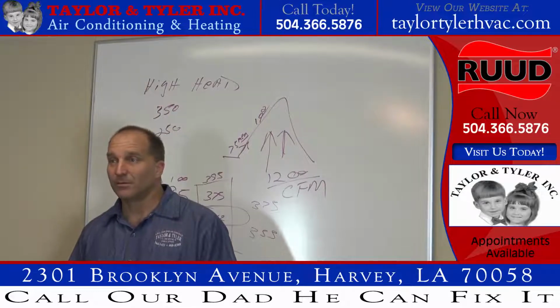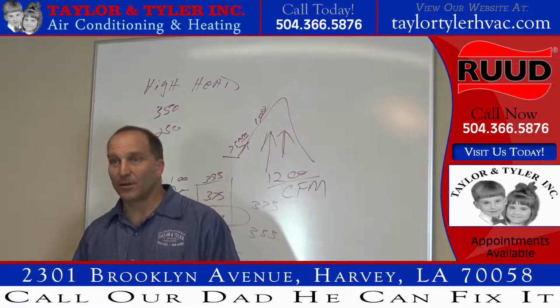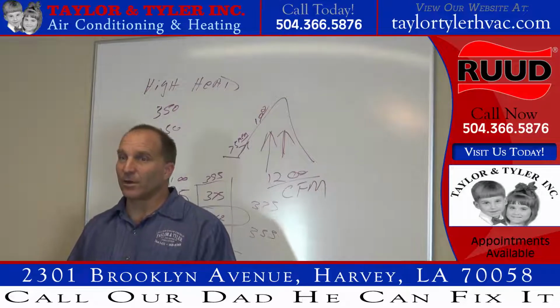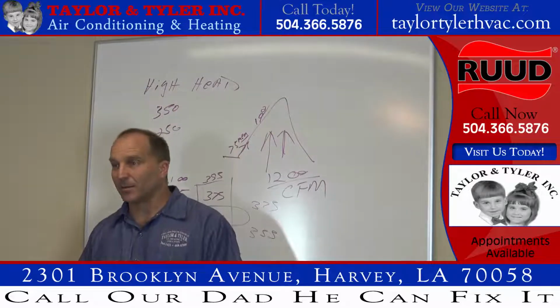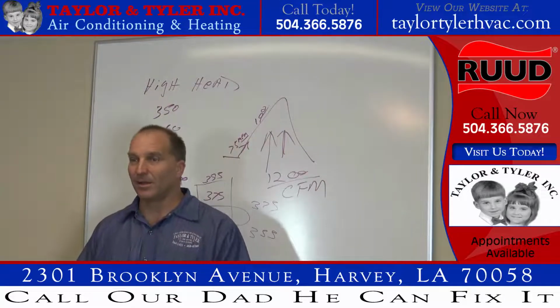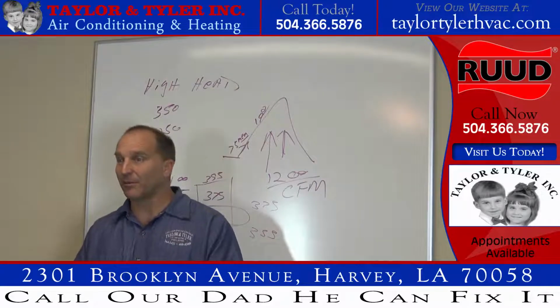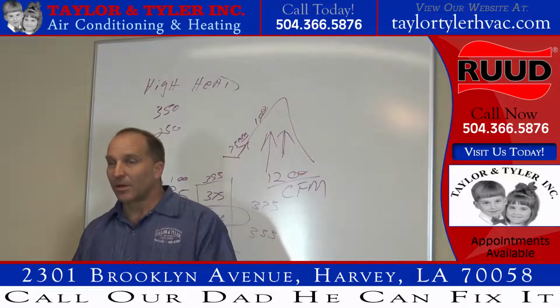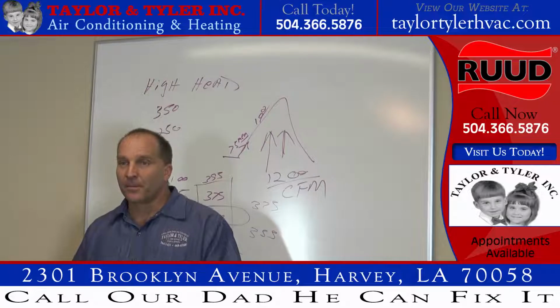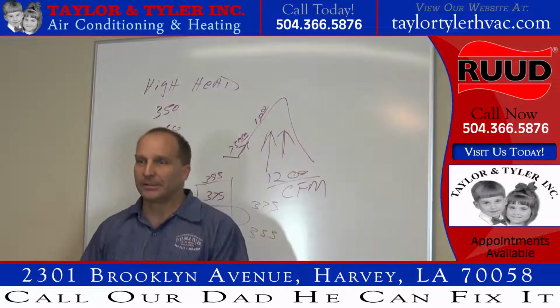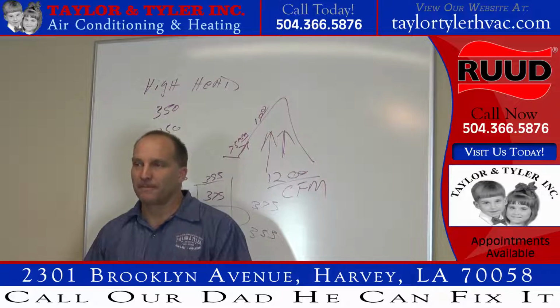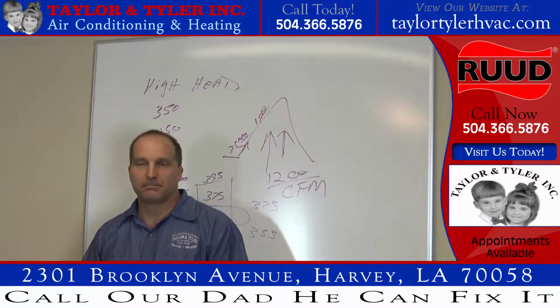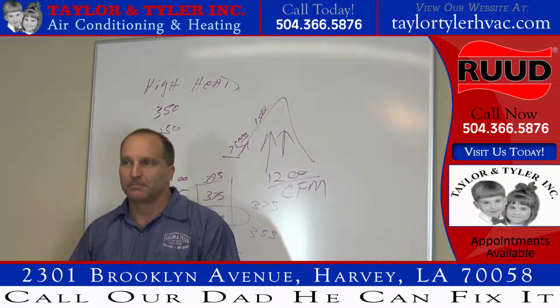So what do I do? Keep adding a little bit of refrigerant, going, if I keep adding refrigerant, that head pressure's got to come up. The suction pressure's going to have to come up. I don't know where this refrigerant's going, but it's going to have to come up eventually. So I keep adding it, and all of a sudden I hear a noise. What's happening? What happened? Blew a gasket? Nope. What happened?